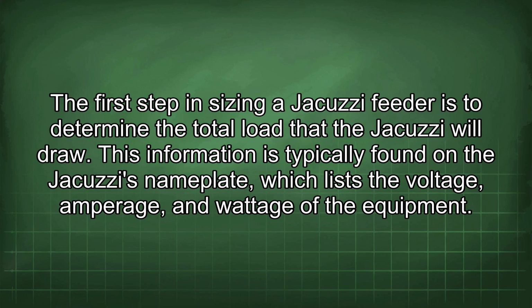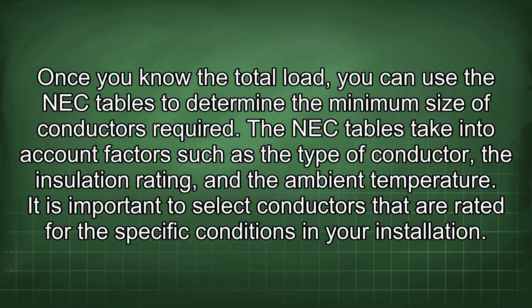jacuzzi will draw. This information is typically found on the jacuzzi's nameplate, which lists the voltage, amperage, and wattage of the equipment. Once you know the total load, you can use the NEC tables to determine the minimum size of conductors required. The NEC tables take into account factors such as the type of conductor, the insulation rating, and the ambient temperature. It is important to select conductors that are rated for the specific conditions in your installation.